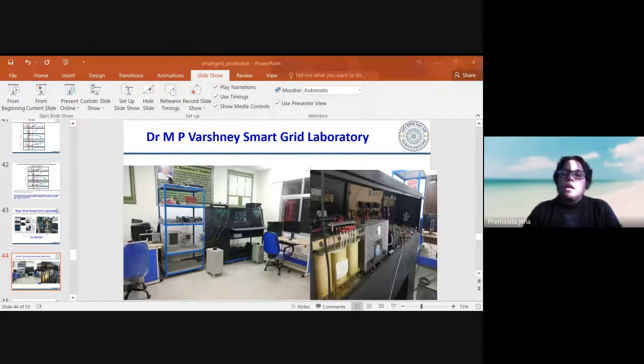And we have to take care of the synchronization process. Afterwards, as far as operation is concerned, the protection system should be relooked at before connecting renewables, because earlier the distribution network had unidirectional power flow, no bidirectional power flow, no power circulation — power only flowed from the substation to the load centers. Now renewables are connected at every corner of the network, so power flow can be in any direction and cannot be controlled. So the devices installed will see different levels of current and voltage in different directions. Therefore, devices installed with previous fixed settings should instead operate in adaptive setting mode. That is a major challenge in protection, and that is my field — we are working on it.